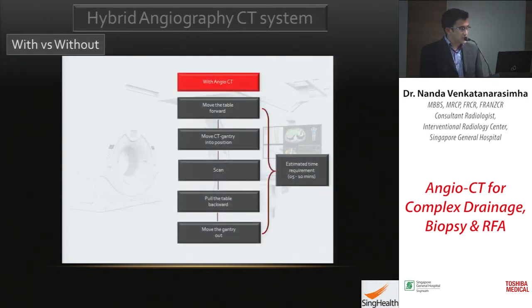So obviously, there are distinct advantages when we use Angio-CT. I'm going to show you the difference between the suite we have, which is the hybrid Angio-CT, and also the one without using Angio-CT, the workflow difference. So with an Angio-CT, especially when you're doing something like the hepatic angiography, which I showed you on the previous slide, once we've done the angiography and place the catheter at the suitable position, we just have to move the table forward and move the CT gantry into position, do the CT scan, and then pull the table backwards and move the gantry out, and we can continue with the rest of the procedure.